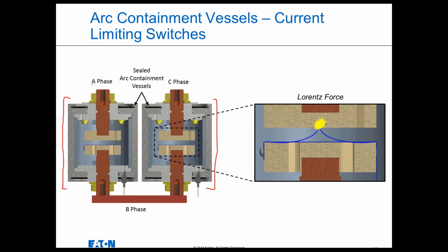In the top of the left arc containment vessel, phase A is tied in. At the top of the right arc containment vessel, phase C is tied in. And phase B is tied into the bottom of both arc containment vessels. These tan things shown here are contacts. If this were a bolted fault device or crowbar device, triggering it when an arcing fault is detected would mean just bringing these two sets of contacts together, clapping them together and creating a zero impedance fault that ties all three phases together.